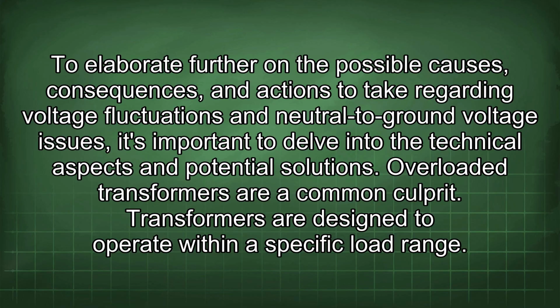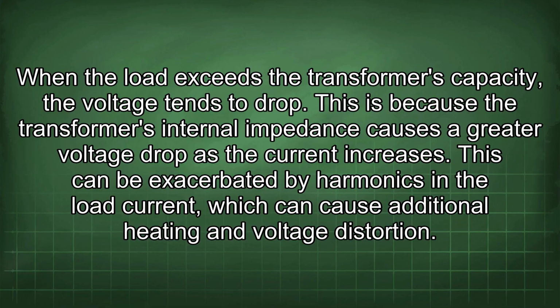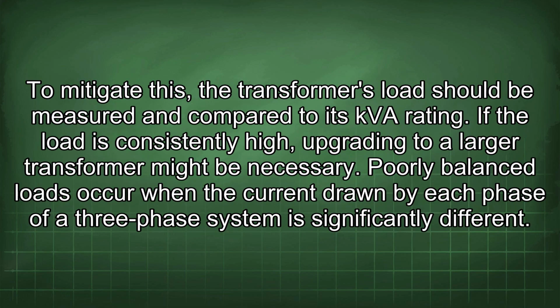Overloaded transformers are a common culprit. Transformers are designed to operate within a specific load range. When the load exceeds the transformer's capacity, the voltage tends to drop. This is because the transformer's internal impedance causes a greater voltage drop as the current increases. This can be exacerbated by harmonics in the load current, which can cause additional heating and voltage distortion. To mitigate this, the transformer's load should be measured and compared to its kVA rating. If the load is consistently high, upgrading to a larger transformer might be necessary.